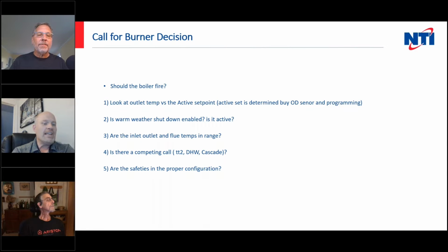Make sure you do, again, no competing calls, because a competing call could override the one that you're expecting to have happen. And then safety's in the proper configuration. Hopefully they're in the proper configuration when you get the boiler, but there are, of course, times when you add safeties because the inspector or the job requires them. So make sure that they're set up properly.